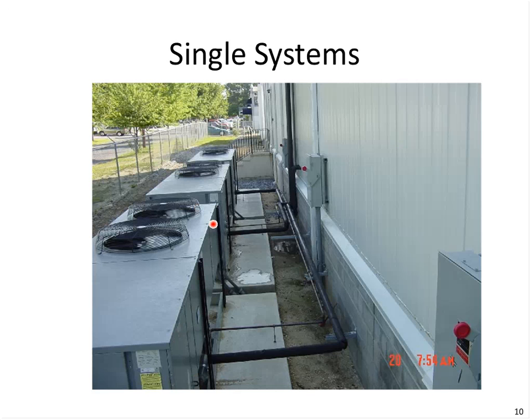So we've got three individual units. These are typically ordered from the catalog. Not necessarily the most efficient, as a result, only used up to maybe a 50,000 square foot facility. Good news is they're readily available, prepackaged, fairly easy to service. On the other hand, fairly short life, not being efficient, and generally you don't see ammonia used in systems like this. Although, with the advent of the micro-channel condenser, that would be a cast aluminum condenser, we just may see some smaller ammonia systems showing up in some of our warehouses.